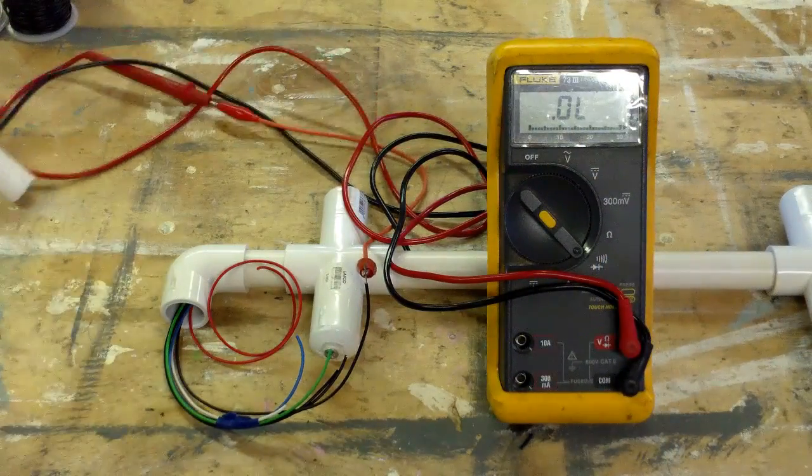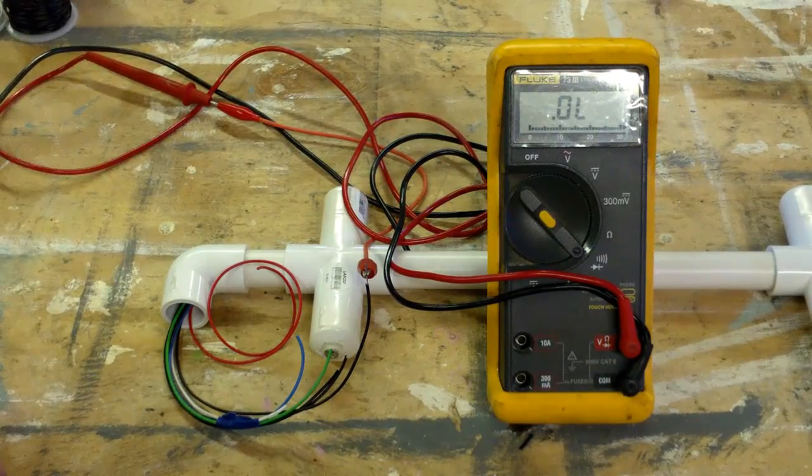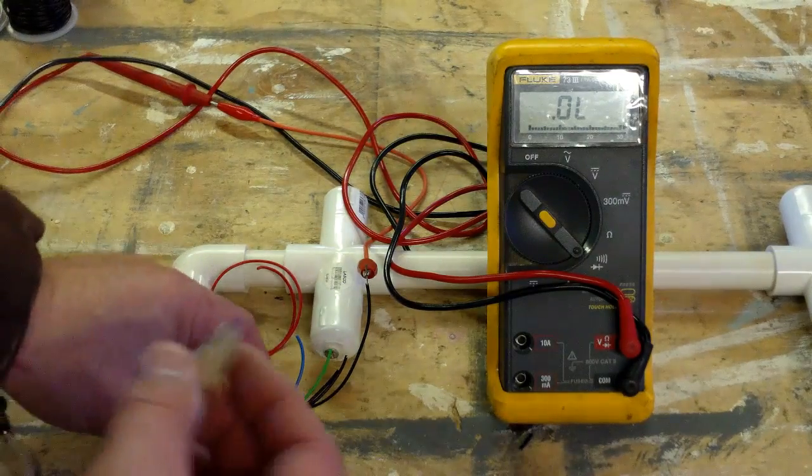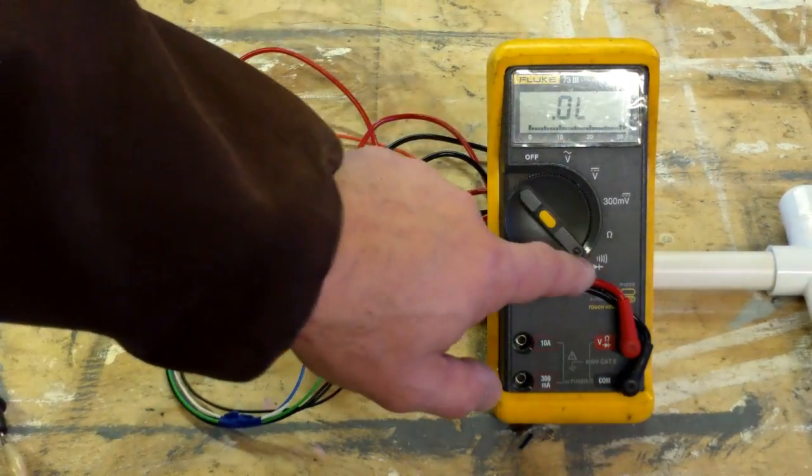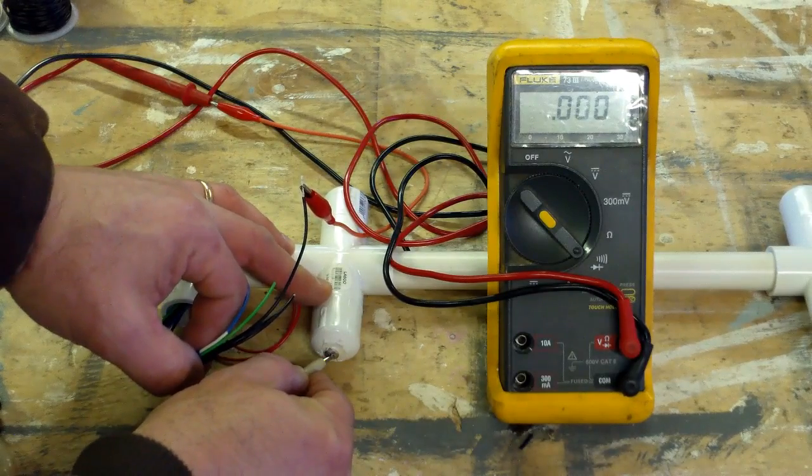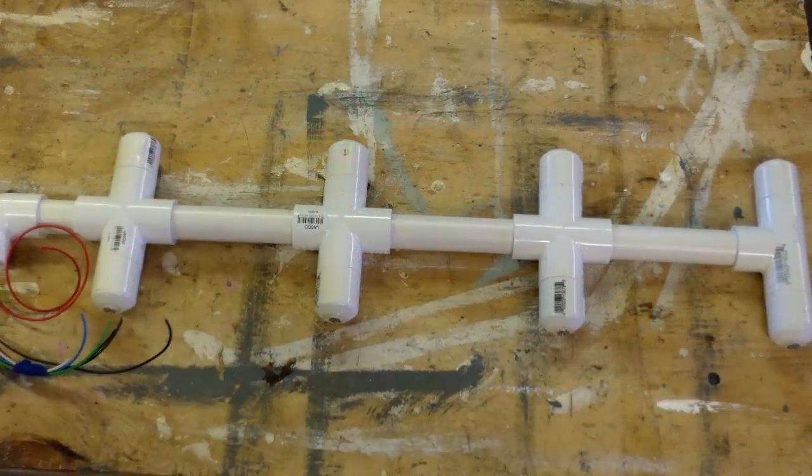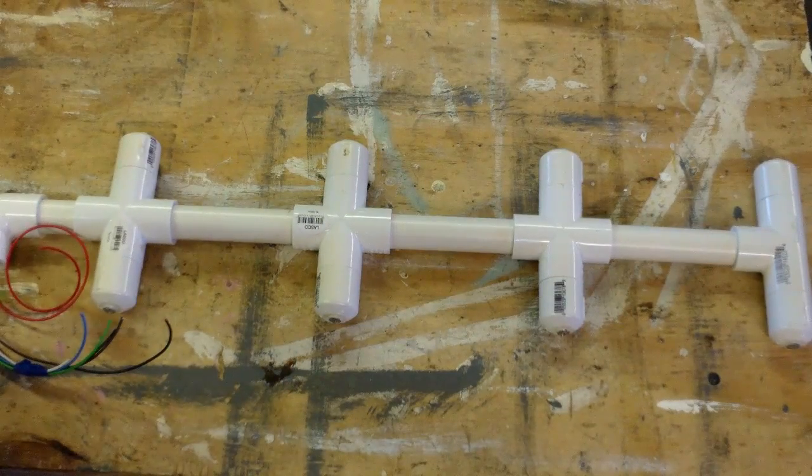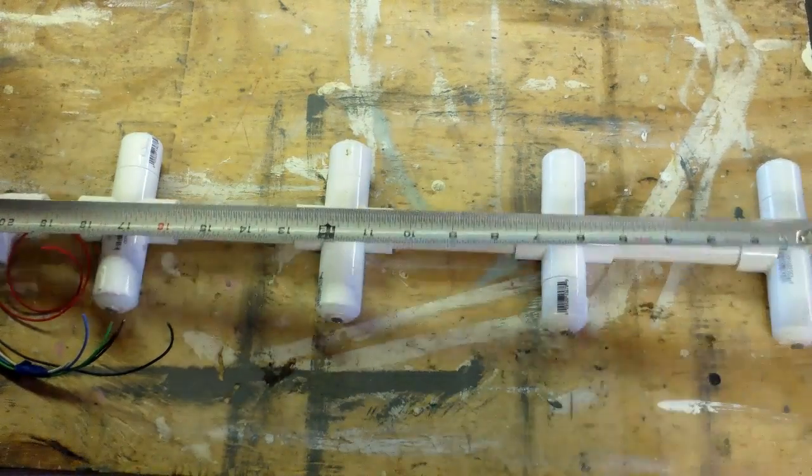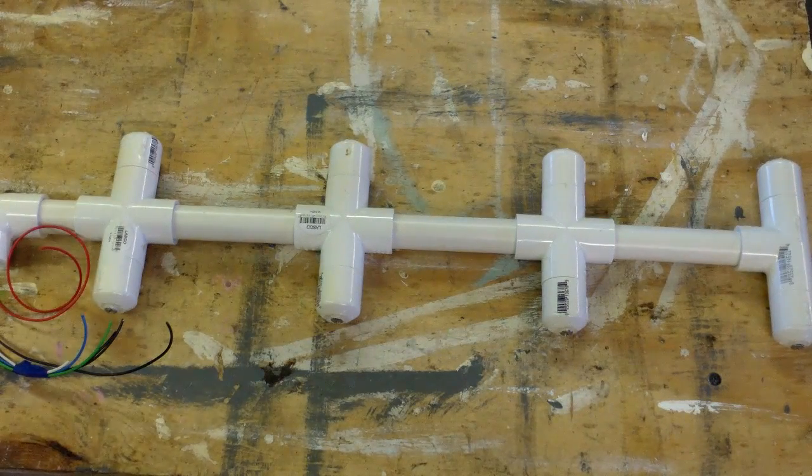Once you get everything dry fit and assembled, one of the things you're going to want to be sure and do is to check the continuity of each of these leads. Because once you get it glued together there's no going back and fixing it. You'll just have to start over. So what I do is I just take a multimeter, set it on the continuity testing and then just go down with some alligator clips and just make sure each one of the wires is making a good contact to the screw. Okay, so now I've got everything kind of dry fit here together. It's all assembled. I needed it to be 21 inches total length. I'm looking good on that. Check continuity. So now I'm ready just to start gluing everything together.